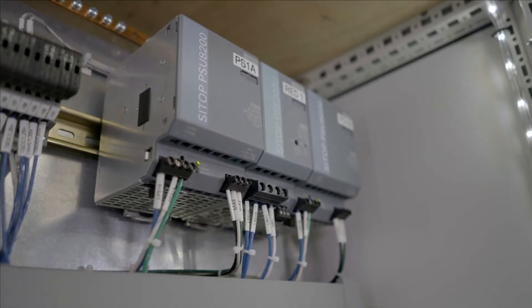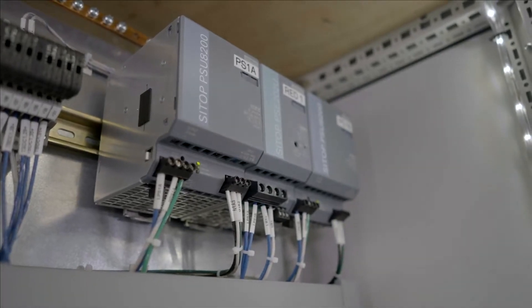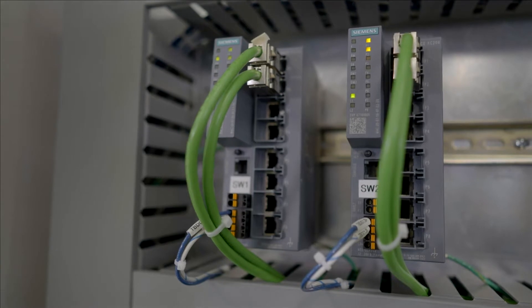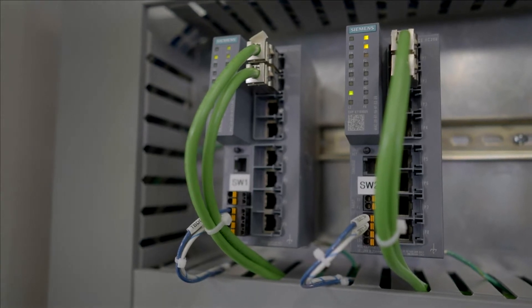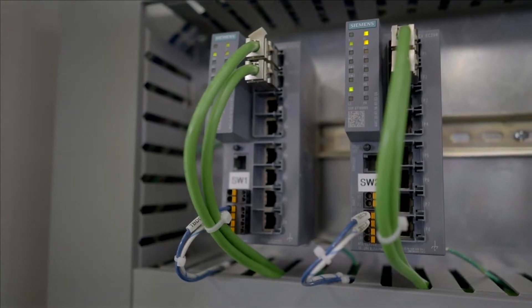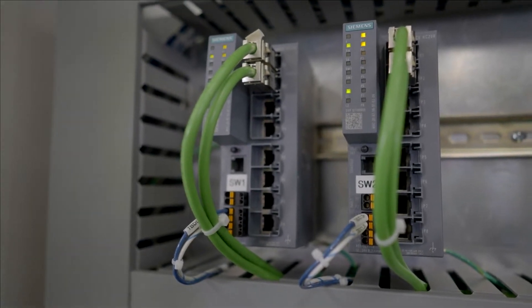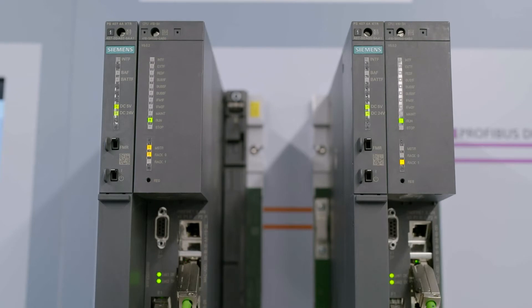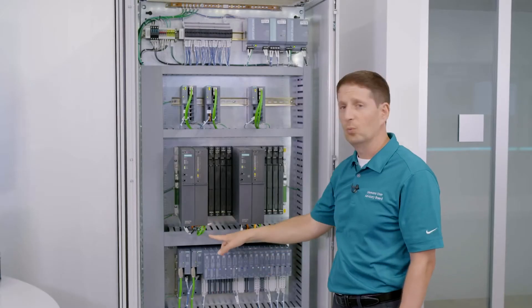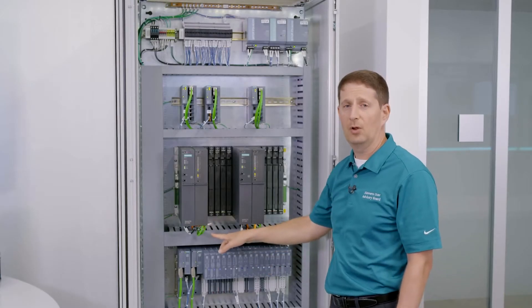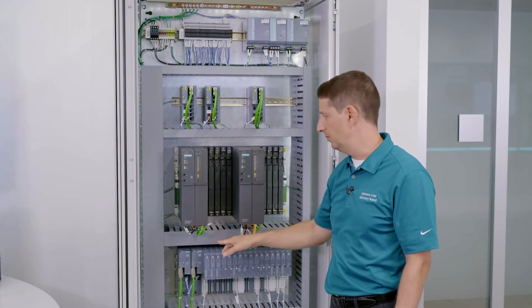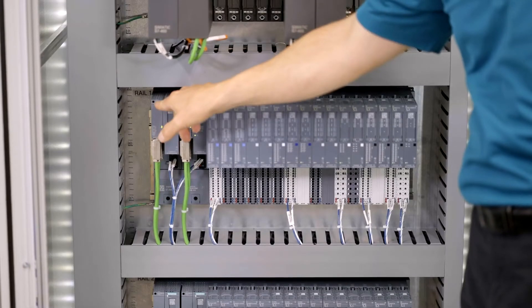We're using redundant power supplies, which are going to redundant industrial SCALANCE switches, which then communicate to our redundant AS410 controller pair. From there, we're going out via redundant PROFINET to the I/O rail.